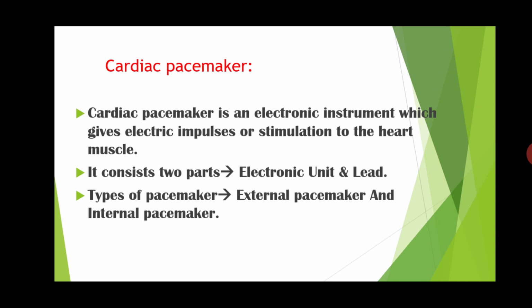Pacemaker is an electronic instrument which gives electric impulses or stimulation to the heart muscles. A pacemaker basically consists of two main parts. First is the electronic unit which generates stimulation impulses of a controlled rate and amplitude, known as the pulse generator. Second is the lead, which carries the electrical pulses from the pulse generator to the heart.